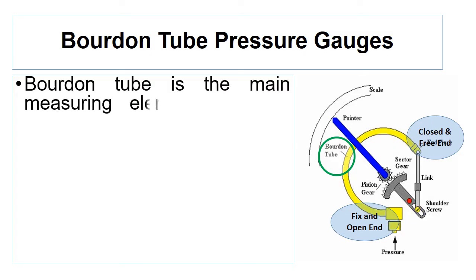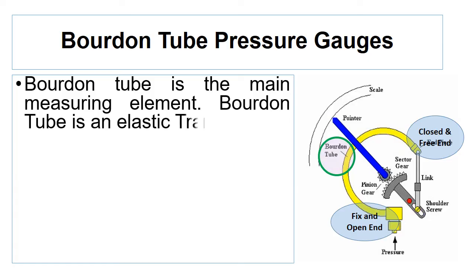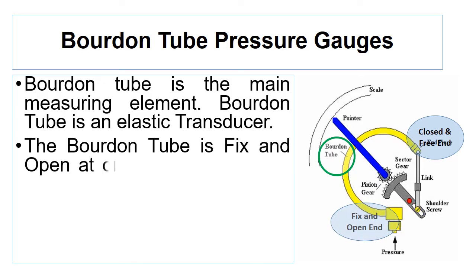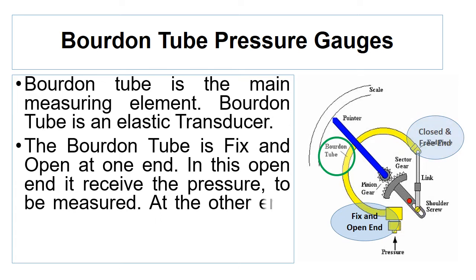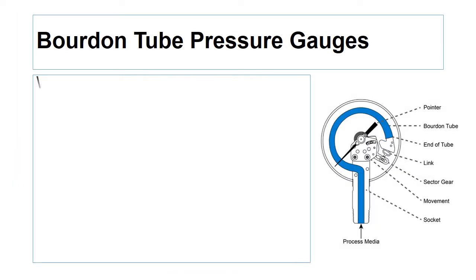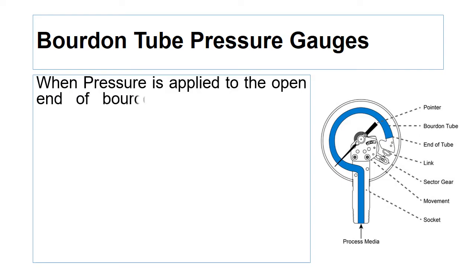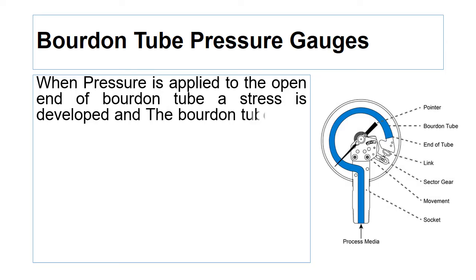In the Bourdon tube pressure gauge, the Bourdon tube is the main measuring element — we can say the Bourdon tube is an elastic transducer. The Bourdon tube is fixed and open at one end, where it receives the pressure to be measured. At the other end, the tube is closed and free for movement. When pressure is applied to the open end, a stress is developed and the Bourdon tube tries to straighten up.